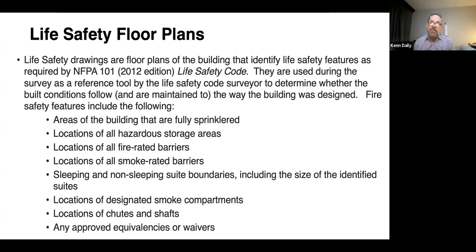Like yesterday, I was in a building and I got to a set of double doors, and I'm like, oh, it looks like some double doors. They're labeled as smoke doors, and I get that. But then maintenance says, Ken, these aren't even on the drawing. The reason they weren't on the drawing as a barrier is that they have no wall above them. So I'm like, I'm glad you know that, because there are buildings that don't know that. So you need to know where your barriers are, making sure you identify those for the survey and on the drawing itself.